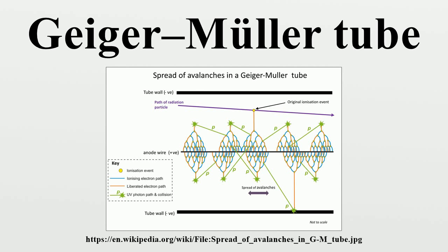In this plateau region, the potential difference in the counter is strong enough to allow the creation of multiple avalanches. Below the plateau, the voltage is not high enough to cause complete discharge, and individual Townsend avalanches are the result. The tube acts as a proportional counter. If the applied voltage is higher than the plateau, a continuous glow discharge is formed and the tube cannot detect radiation. It is normal to operate the tube in the middle of the plateau so that variations in the voltage of the tube do not take it out of the Geiger operating region.